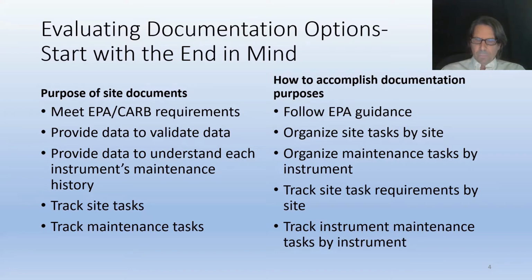And for smaller organizations that don't move their equipment around, the same style system will typically address both of these purposes. But for larger organizations that do move their instruments around, it's important to realize that your documentation system has to be capable of organizing the documents by site and by individual instrument, regardless of where that instrument was located.